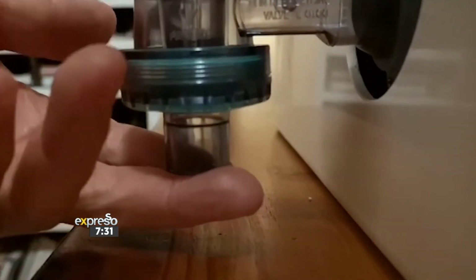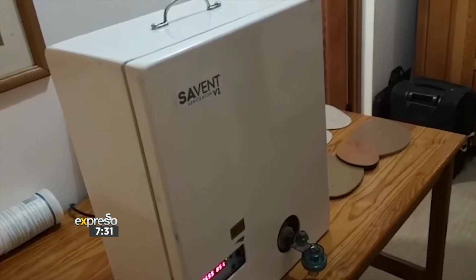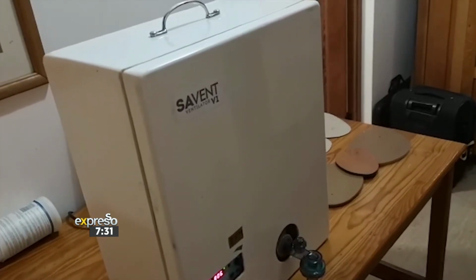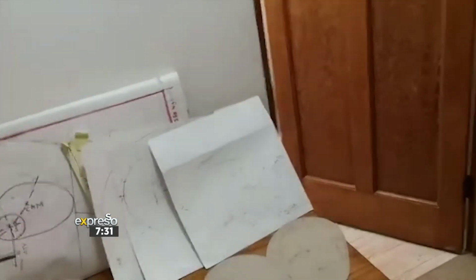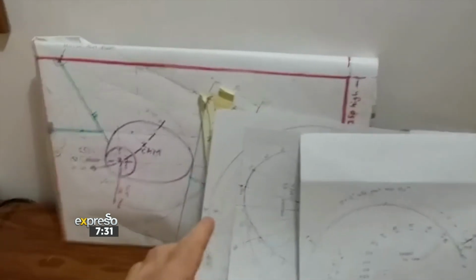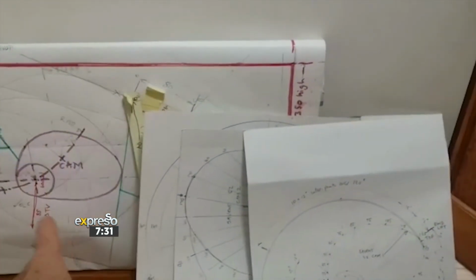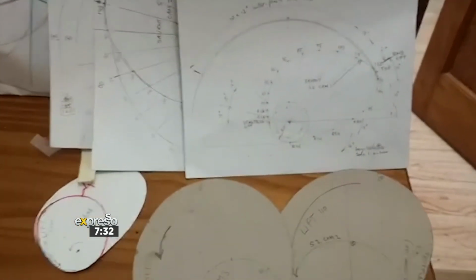Talk to me about the work process of creating this machine, because you must have worked tirelessly, having taken less than 2 months, I understand, to start and complete the prototype. Yes, we set the objective to do three things. One was the breathing rate at about 20 breaths a minute, and we found we could make that speed adjustable. The second was the volume of about 500 milliliters per breath, and the third was what they call the IE ratio, which is the timing for breathing in and breathing out.